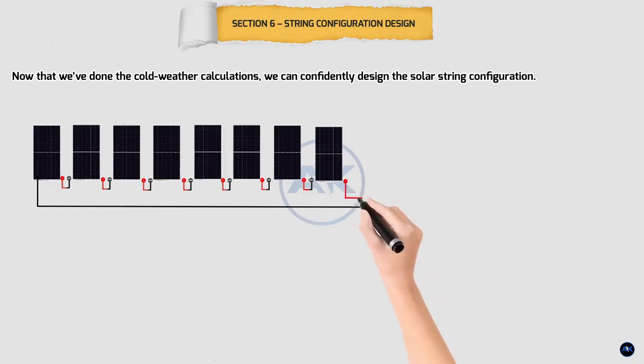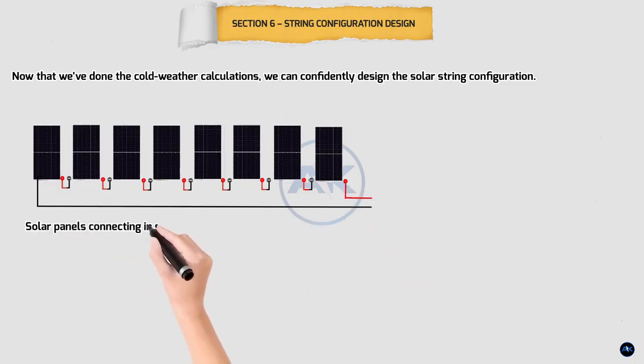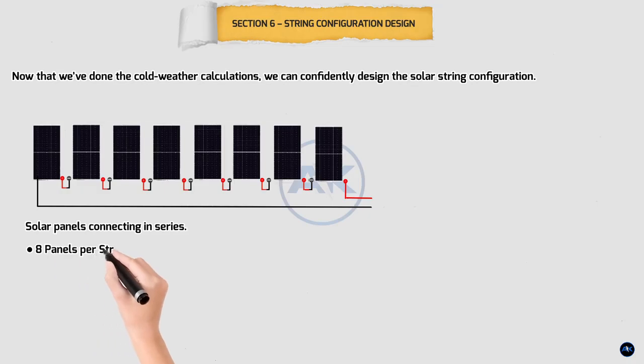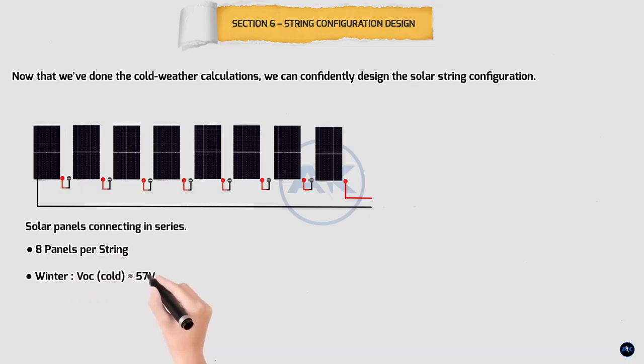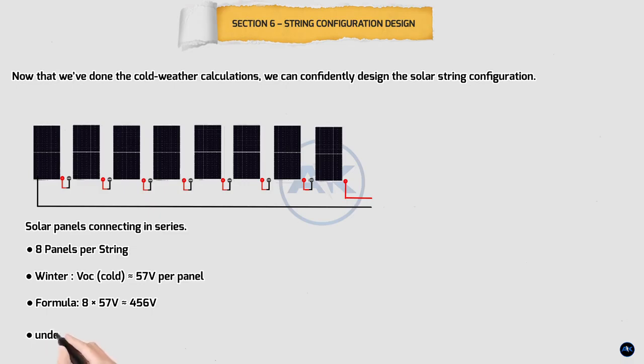Let's verify this design by checking both voltage extremes. First, cold weather open circuit voltage. At -20 degrees Celsius, each panel produces about 57 volts. With 8 panels in series, the total string voltage is 8 multiplied by 57, which equals approximately 456 volts. That stays below the inverter's 500-volt maximum limit, so the system is safe in winter.